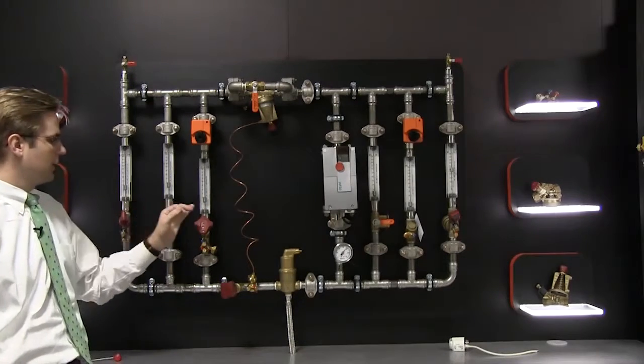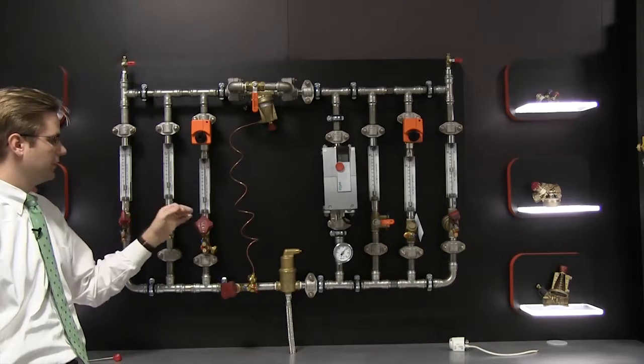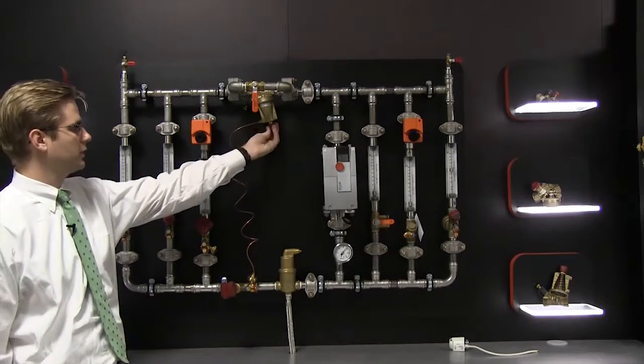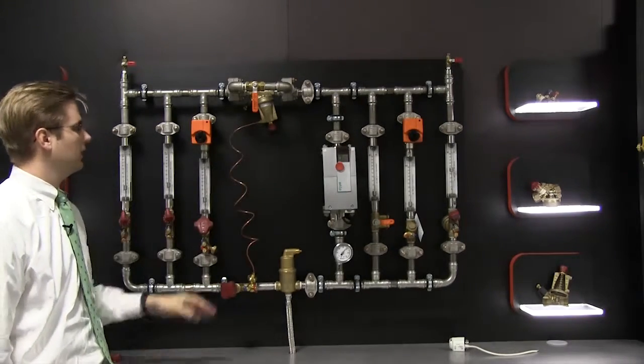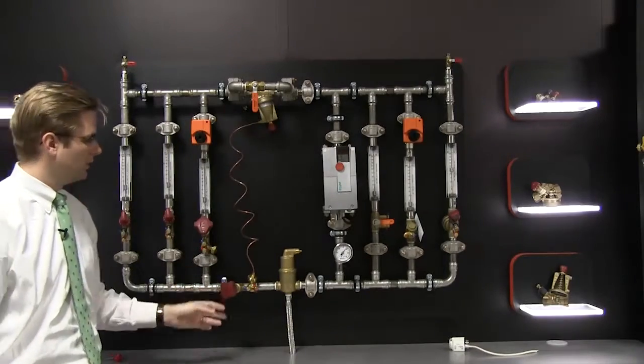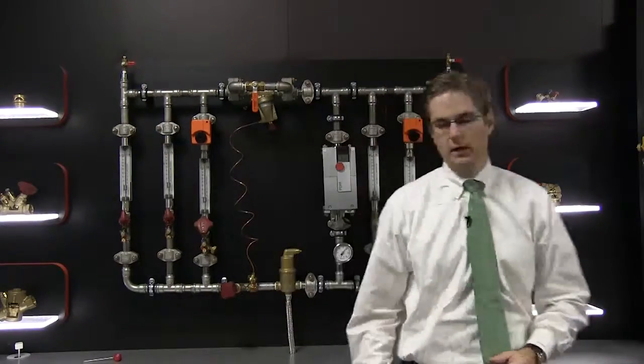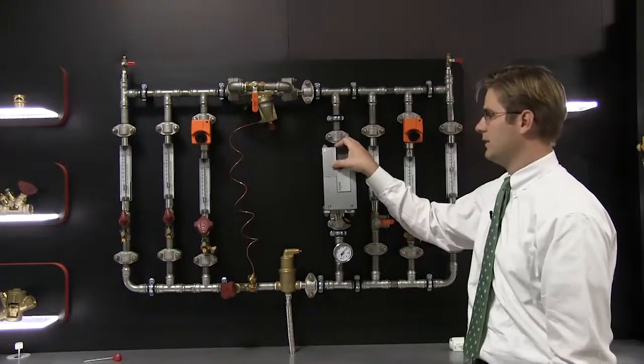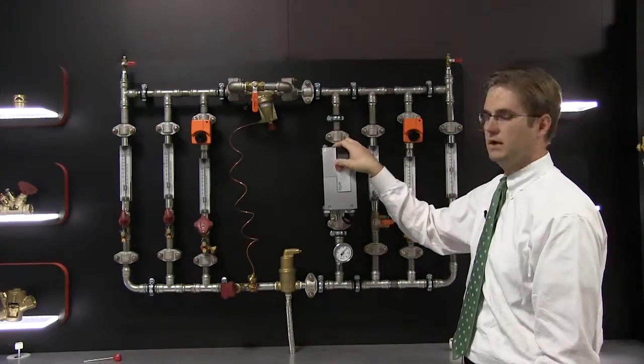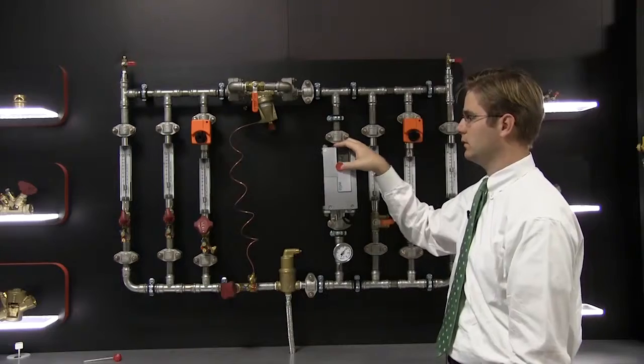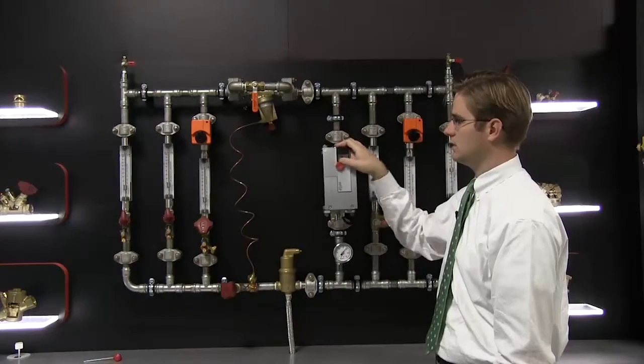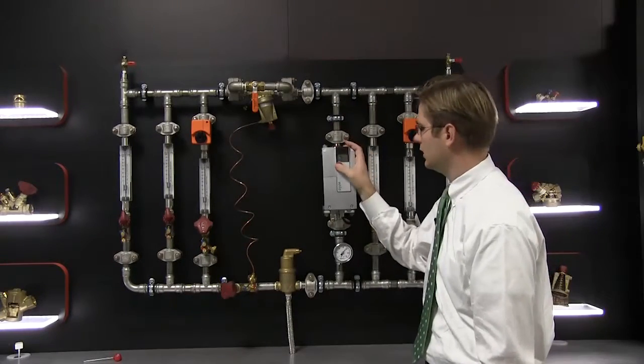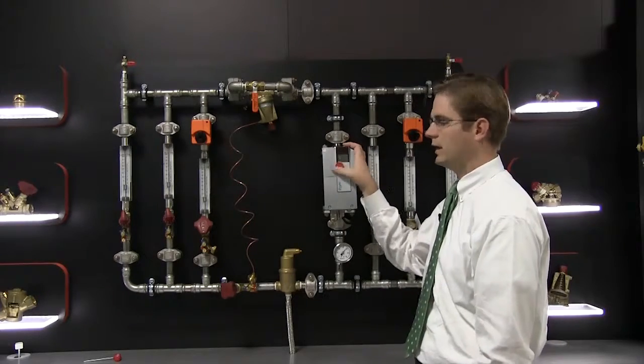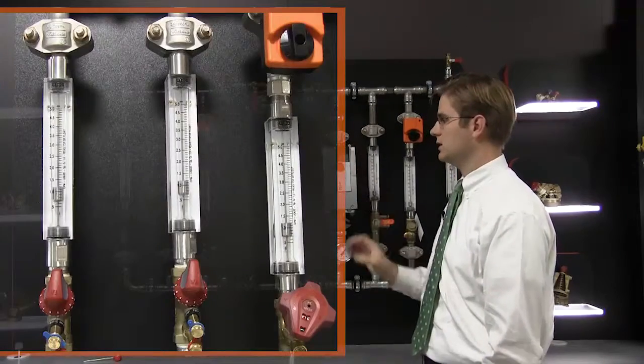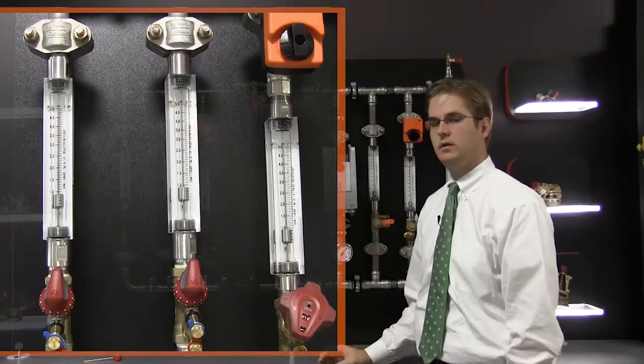I have all these 3 manual balancing valves set at 1 GPM. I have our differential pressure control valve open and the bypass around it closed. What you'll notice when I increase the speed of the pump is that the terminal units will all stay relatively the same. So I'll increase the speed of my pump from a mid-range setting all the way to 4,800 RPMs. And you can see the flow rates increase for a moment and then maintain a constant 1 GPM.